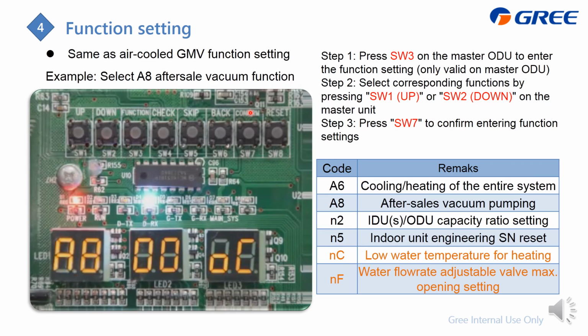So for the GMV water, here are all the function codes we are going to talk about this time. A6 is to select the whole system, either cooling or heating of the system, and A8 is after sales vacuum pumping. That means if you select this one, we will turn on all the solenoid valves and the EXV, to ensure there's no dead zone in the system.